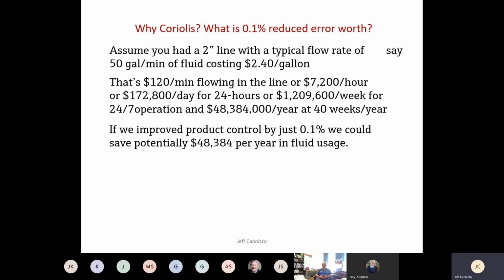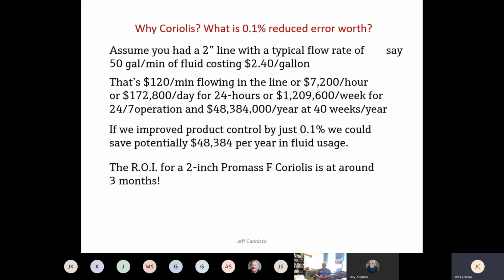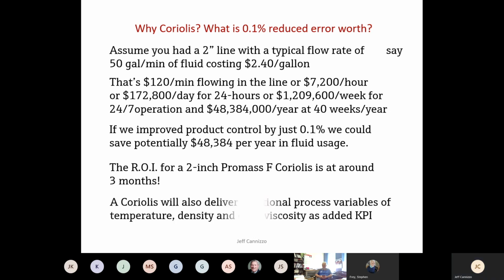And a Coriolis meter, it's always going to depend on materials of construction, but the return on investment for a 2-inch meter could come in at around 3 months. So you can see that it's worth it in many cases to make that initial investment. And even if your product costs $1 a gallon, 80 cents a gallon, you're still getting a real good return on investment from a Coriolis meter. Plus, you always get the additional process variables, the temperature, the density, and potentially even the viscosity if you need it.